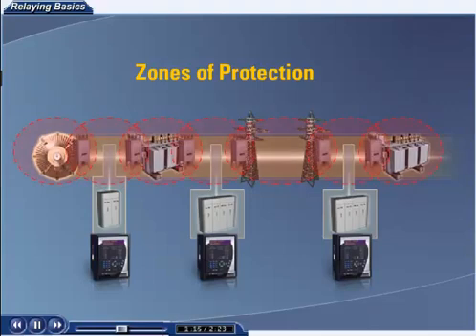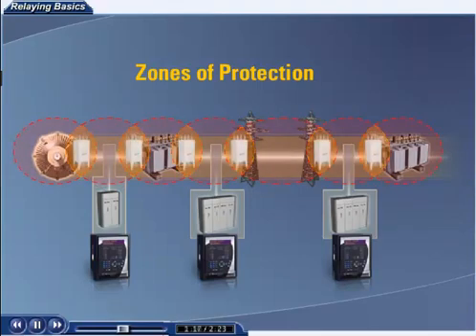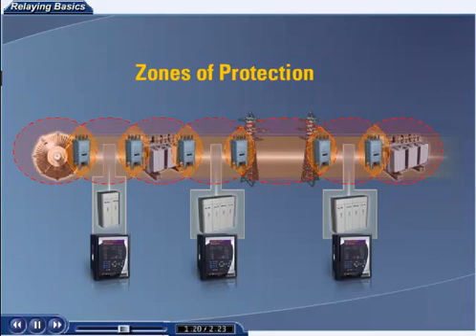For failures within the overlap area, more breakers will be tripped than needed to disconnect the faulty element. However, the overlap areas are relatively small, and the probability of failure in this region is very low. Therefore, the tripping of too many breakers for a fault in the overlap area will be infrequent. The preferred practice is that adjacent protective zones overlap around the circuit breaker, so that for failures anywhere other than in the region of the overlap, the minimum number of circuit breakers will be tripped.